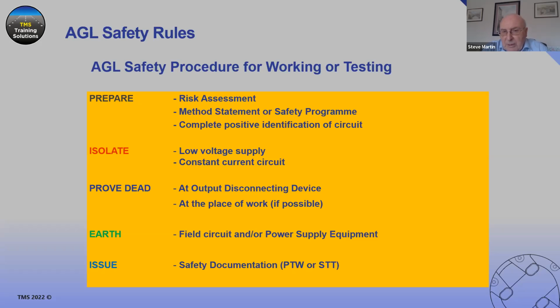Then we can earth the circuit, either the field circuit if we're working in the field, or if we're working in the AGL switch room vault, then we may be able to earth the power supply equipment to prevent any charge build-up. And then again, issue the safety document.